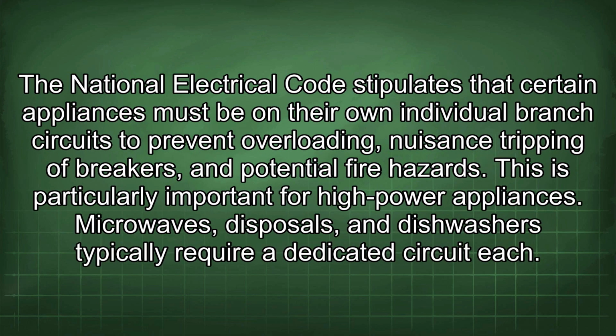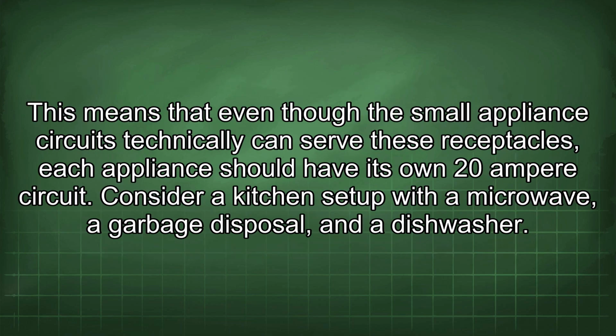The National Electrical Code stipulates that certain appliances must be on their own individual branch circuits to prevent overloading, nuisance tripping of breakers, and potential fire hazards. This is particularly important for high-power appliances. Microwaves, disposals, and dishwashers typically require a dedicated circuit each. This means that even though the small appliance circuits technically can serve these receptacles, each appliance should have its own 20-ampere circuit. Consider a kitchen setup with a microwave, a garbage disposal, and a dishwasher.